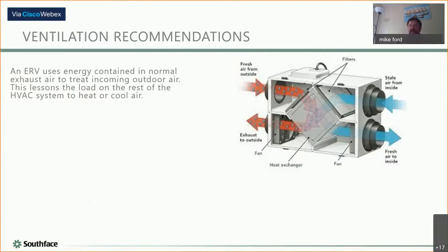So I'm just going to name a couple things we talk about a lot in this world of energy efficiency. First is an ERV, an energy recovery ventilation unit. Air is being exhausted from the space, conditioned heated air, for example. It doesn't actually cross with the incoming air directly, but there's a transfer of energy, an exchange. Some of that warmth going out transfers its energy to the cool air coming in, so when that cool air goes into the furnace to be heated, it already reduces the load on your HVAC system.